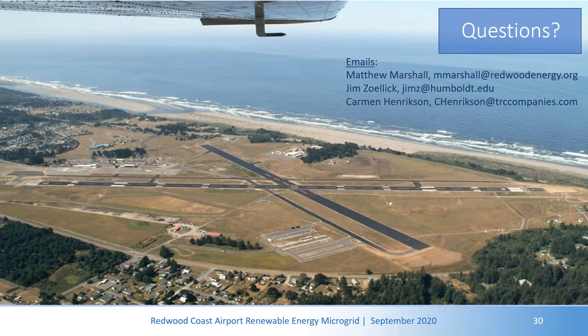So when we go into island mode, PG&E has responsibility, but there's really no control of those assets. It's all automated. When we go into island mode and the recloser opens, whether it's a seamless transition or a break-before-make transition, Tesla's battery system will form the microgrid and then meet the load. Obviously the generation needs to meet the load, otherwise you have problems with voltage and frequency deviations and things go south very quickly. So the generation is going to exactly meet the load. There's no controlling how much generation we're producing.